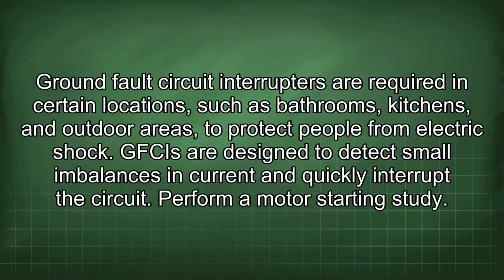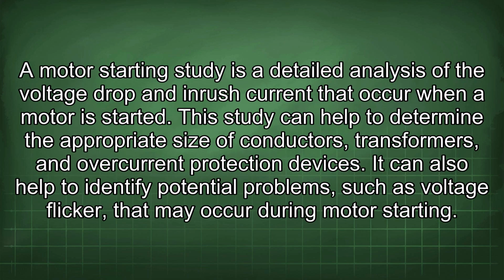Perform a motor starting study. A motor starting study is a detailed analysis of the voltage drop and inrush current that occur when a motor is started. This study can help to determine the appropriate size of conductors, transformers, and overcurrent protection devices. It can also help to identify potential problems such as voltage flicker that may occur during motor starting.